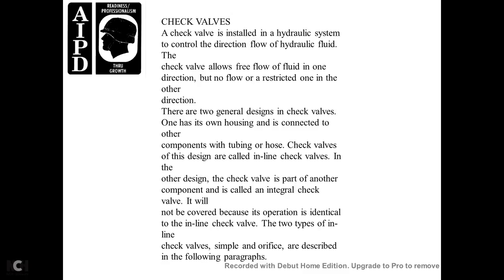Check Valve. A check valve is installed in the hydraulic system to control the direction of hydraulic fluid flow. The check valve allows free flow of fluid in one direction but restricts or blocks flow in the opposite direction. There are two general designs of check valves. One has its own housing connected to other components by tubing and hosing; these are called inline check valves. The other design, where the check valve is part of another component, is called an integral check valve. The two types of inline check valves are simple and orifice types.